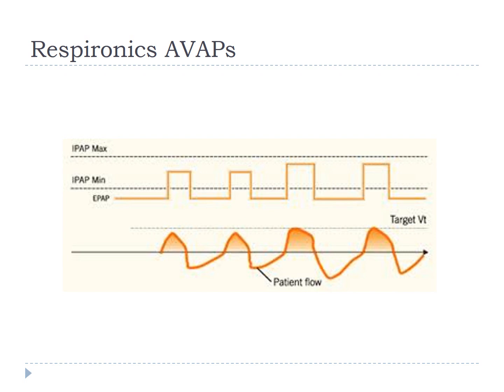And then on the next breath, it delivers a higher pressure, and finally that patient's target tidal volume is reached. So it takes longer for the patient to get to the pressure that fixes their breathing with the AVAPs because it takes a longer time to respond, but this one is based more on the tidal volume and the minute ventilation as opposed to flow. Let's go on.